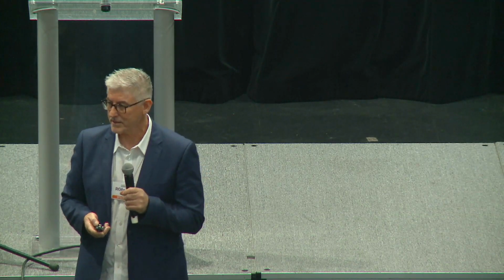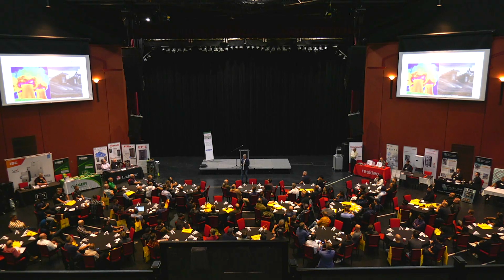non-compressor-based cooling systems. This one here was at one of the universities. Peter Rumsey was the engineer on it. What they do during the evening is they spray water up onto the roof, and they cool the water with radiative cooling and evaporative cooling. And they store that chilled water in a cistern. And then during the day, they take that chilled water and cool it with a radiant floor cooling system. No compressors. There's new technology out, and this came, I believe, out of Harvard.